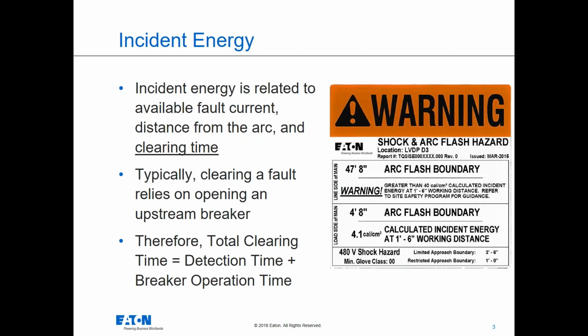Typically, clearing that fault relies on opening an upstream breaker. Fuses get used in a lot of systems nowadays, but they fell out of favor decades ago. So most people design around circuit breakers due to the ease of resettability and service once they've been installed. When we're discussing the clearing time on a circuit breaker, there's two pieces that go into that. Those two pieces are the detection time for whichever trip unit is inside the circuit breaker, and then the mechanical time that the circuit breaker actually takes to open a set of contacts, draw an arc through a set of arc chutes, chop that arc up in the ionized gas, and actually clear the fault and stop the fault current. So that clearing time, combined with the other two elements, is how the incident energy gets calculated.